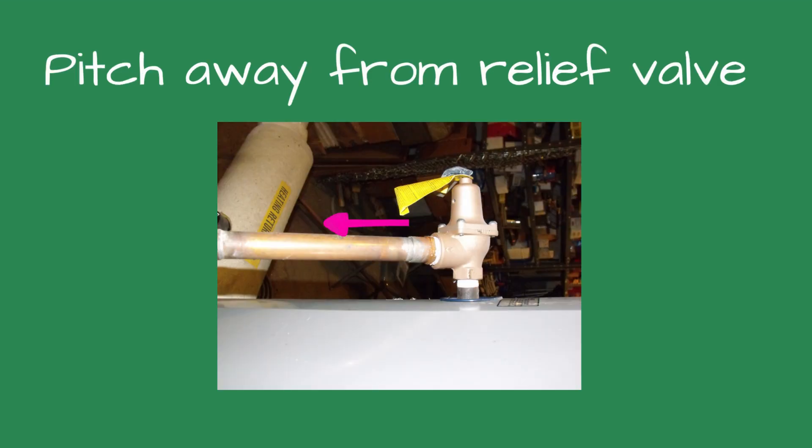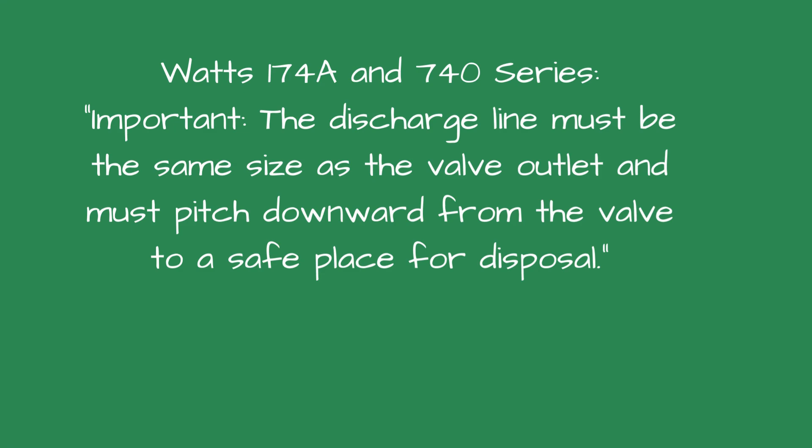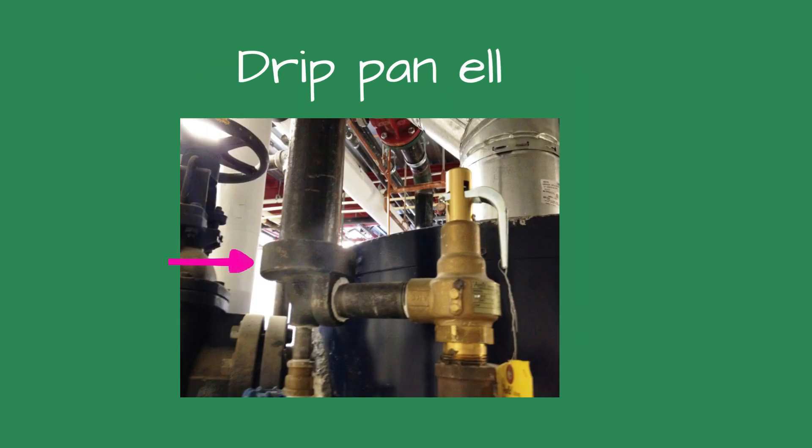Hydronic Relief Valve. The following is what Watts recommends for their 174A and 740 Series Relief Valves. Important: the discharge line must be the same size as the valve outlet and must pitch downward from the valve to a safe place for disposal. You don't want water resting against the relief valve discharge. Steam Boiler. Most boiler manufacturers recommend a drip pan ell be used when the relief valve discharge piping rises. The drip pan ell is used to reduce the weight of the discharge pipe on the relief valve. It also has a drain fitting which will drain any water in the discharge piping. Some codes require the discharge to be vented outdoors.